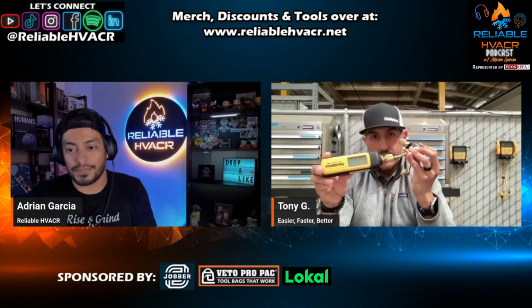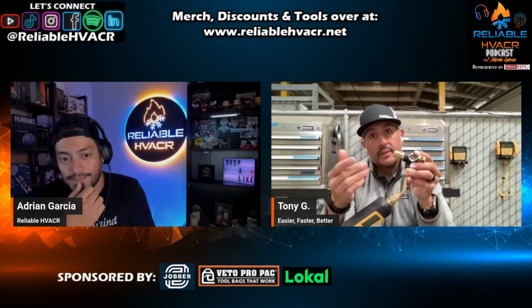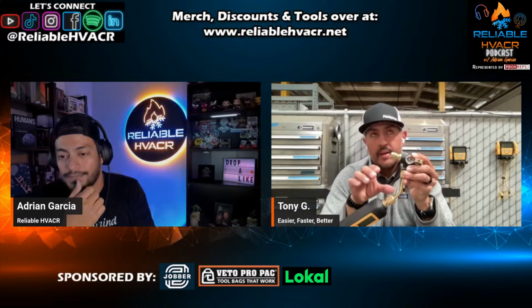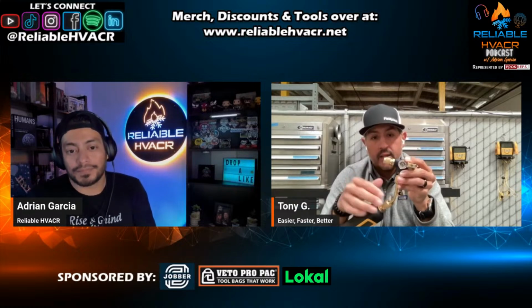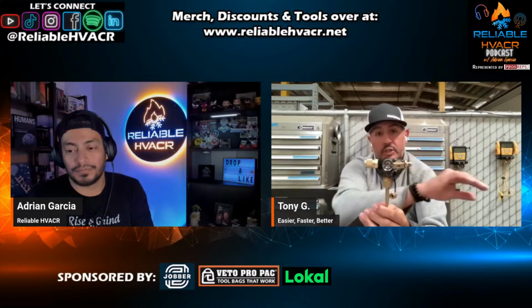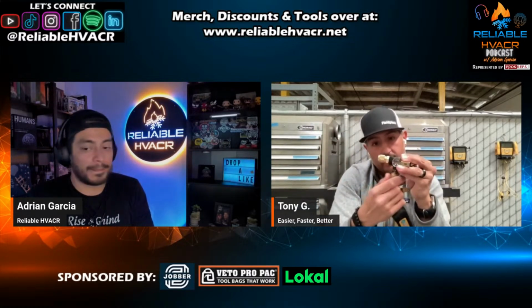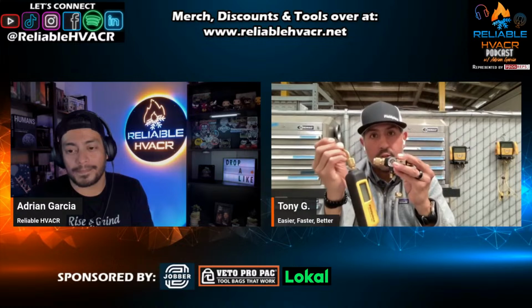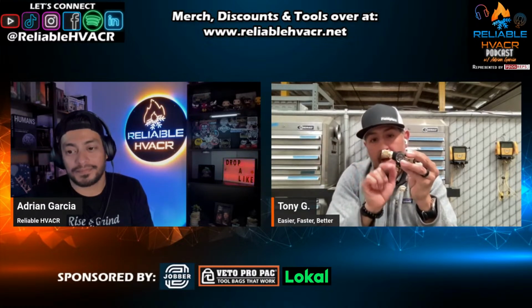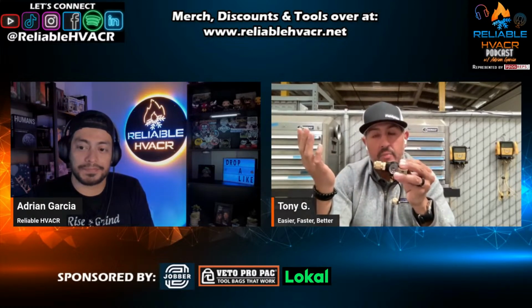For sure. So despite the fact that this micron gauge can take up to 800 psi of pressure, it's not something that I regularly want to expose it to, for the reason that you just said, over time contaminating your sensor with oil or other stuff that is in the refrigerant. So you either have to do two things. You either have to charge it up and then expose this to the refrigerant, or you could say, well, why don't I just disconnect it while the system's under vacuum, and then I don't expose my micron gauge to refrigerant. But what you just did by doing that is you momentarily allowed a little bit of air to go back into here, thus kind of nullifying the vacuum that you just pulled on the system.